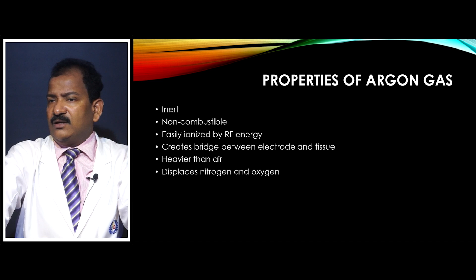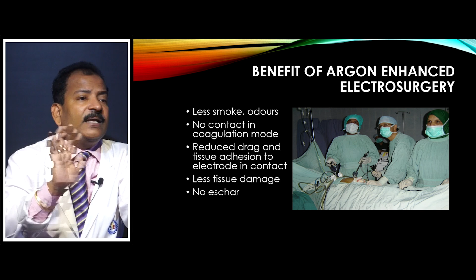The benefit of argon enhanced electrosurgery is less smoke, less odor, you do not need to contact in the coagulation mode because the gas itself is making contact, less tissue damage and no eschar formation, because gas cannot hold any eschar. But it is not for every surgery. You cannot use the argon beamer everywhere, because it cannot cut, it cannot dissect, it can only fulgurate.